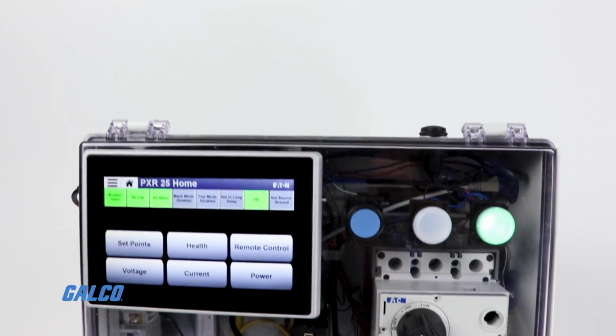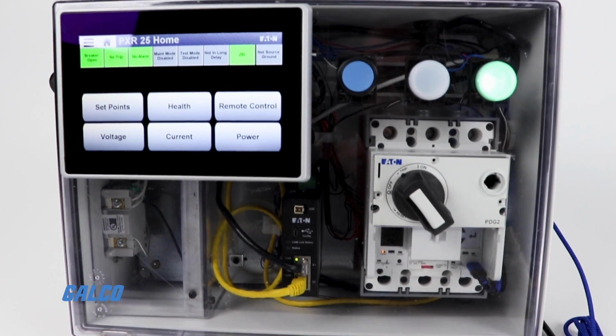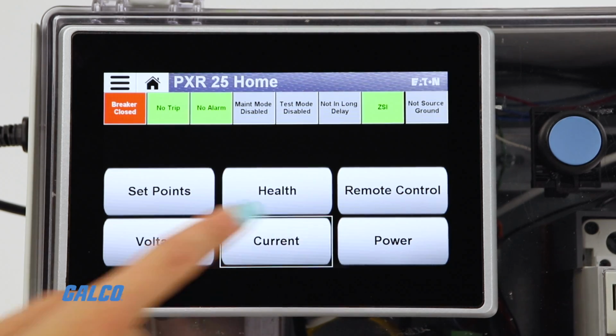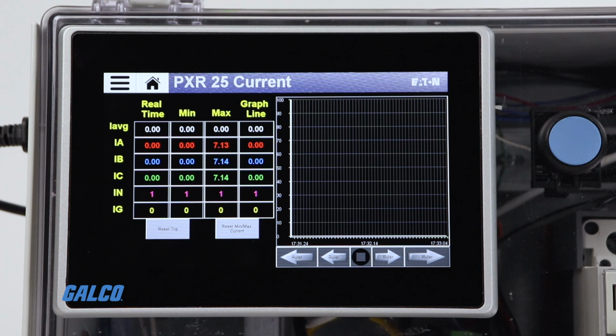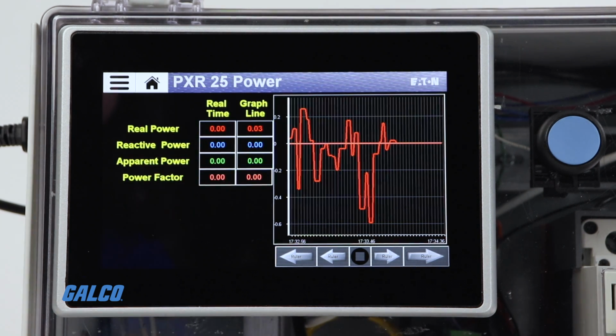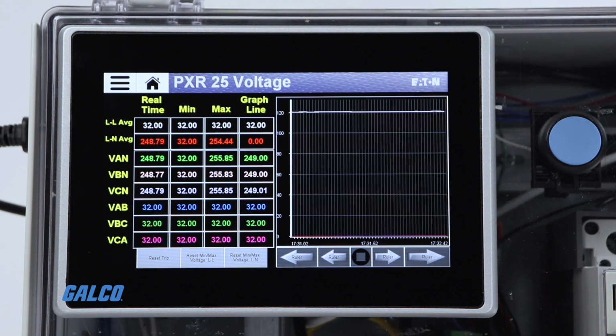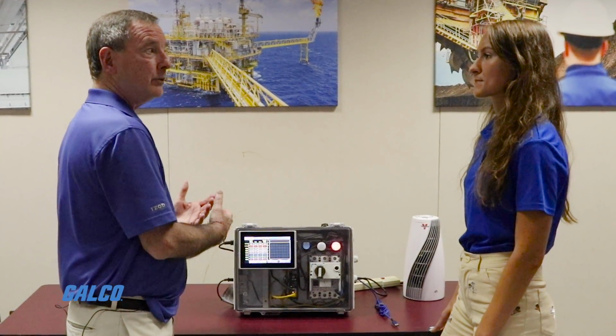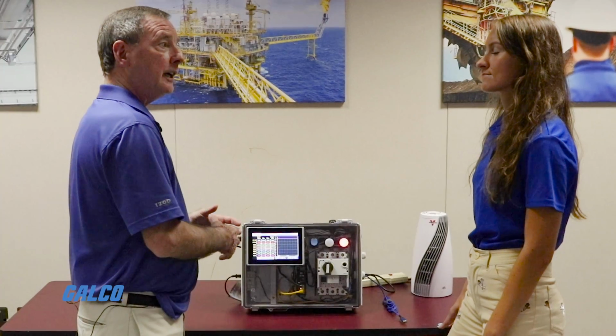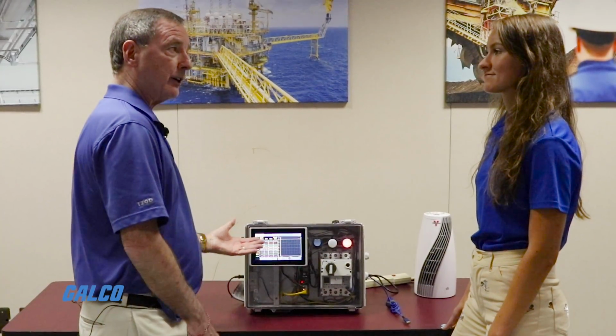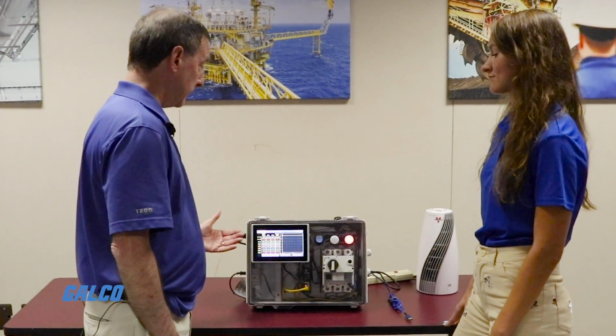So you can measure current, so you know by phase what is the current at each phase, because internally it's using its own CTs, so I can measure phase, I can measure voltage. So it's also giving you voltage. With voltage and current, now I got kW. So I know the energy usage on the load side of this breaker. So if I'm trying to calculate what my usage is on a machine or in a plant, I now get access to every breaker family that I have.